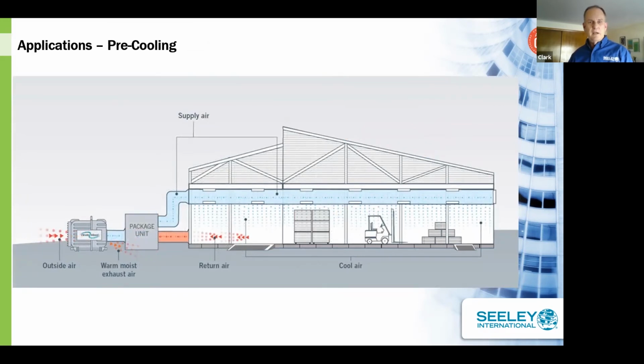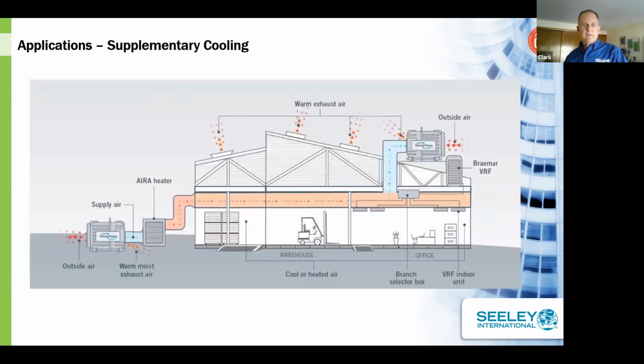If we look at pre-cooling, here's where we're using the Climate Wizard unit to cool that outdoor air, the ventilation air, to a package unit. So this could be an RTU or an air handler. Since we're doing sensible cooling, we're not adding any latent load to this package unit. And this package unit can also have some heat. So in the wintertime, you can use that for heating and then cooling in the summertime.